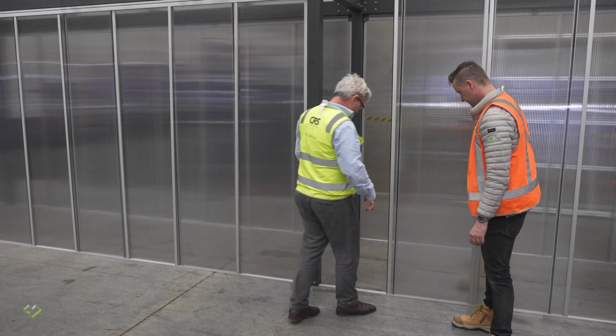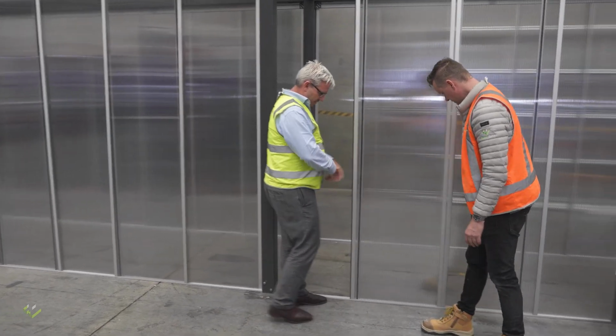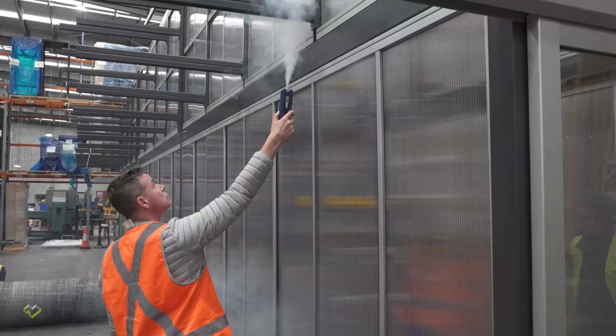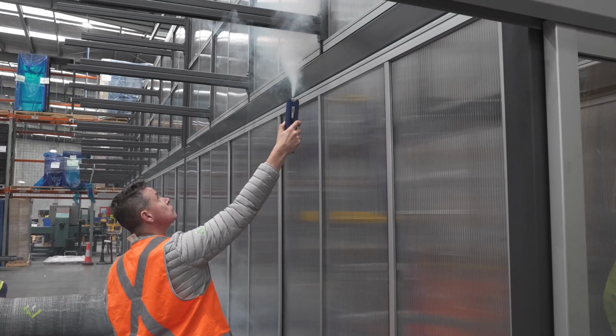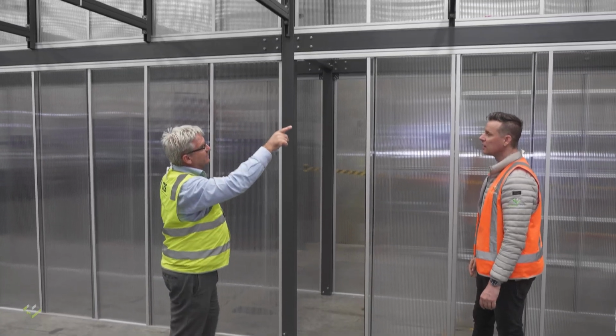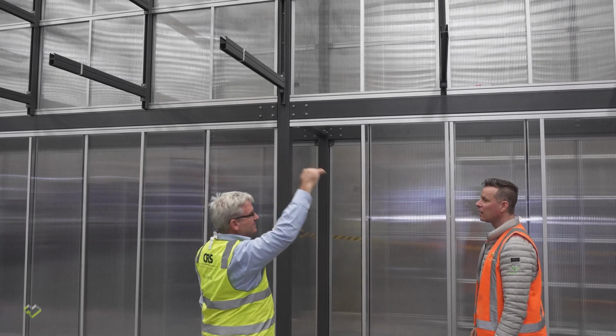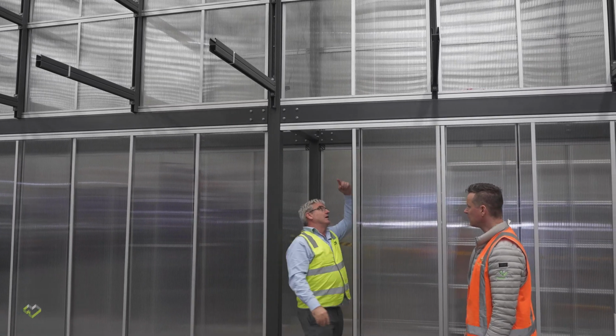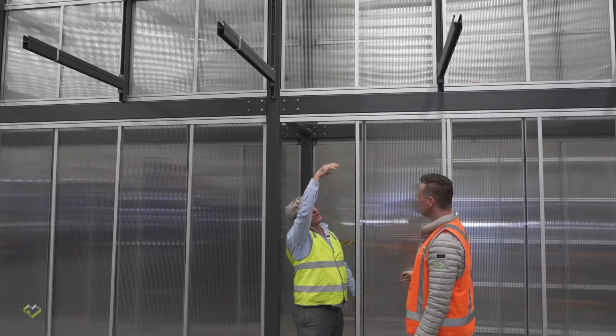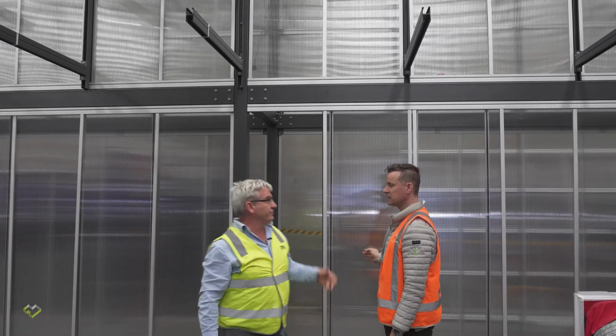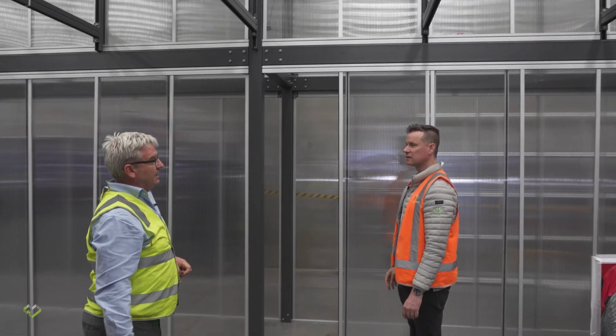How much development have you guys put into this system? A double track system, so you can put racks in, you can double the panels up to slide them out of the way as you put the racks in. And development above there, so you don't have to stand on the racks to open those windows up to get to the cable baskets here. You can simply get in the hot aisle, open the windows up, reach through, work on your services, do whatever you need to do. A lot of development on the sliding doors. Great.